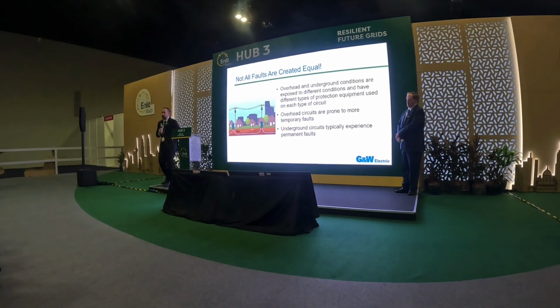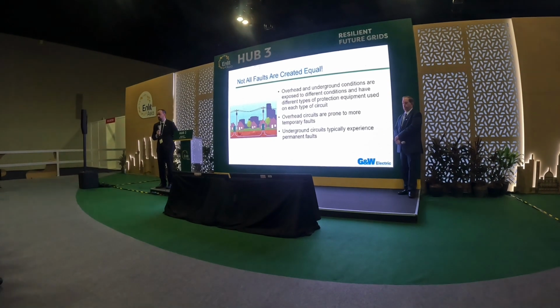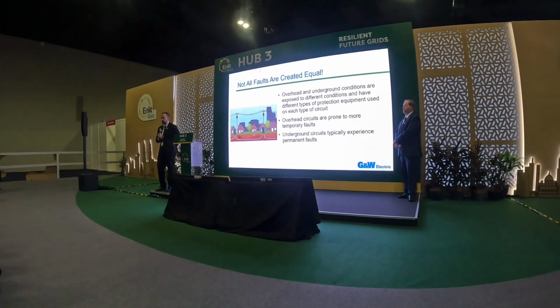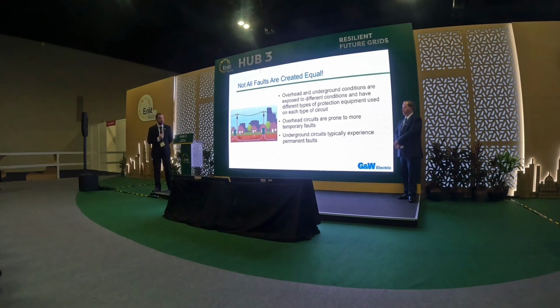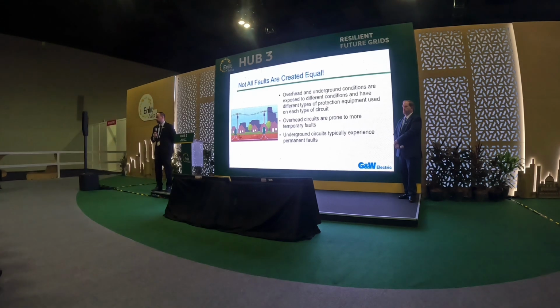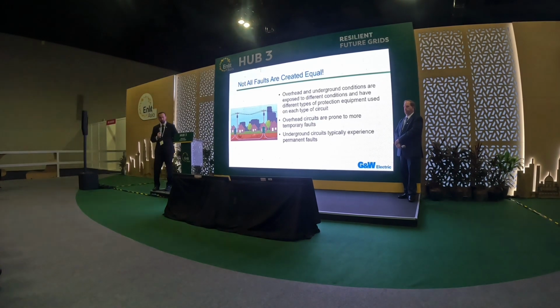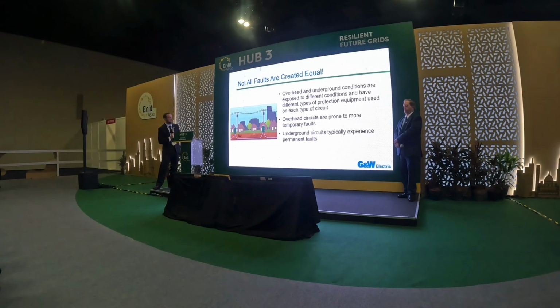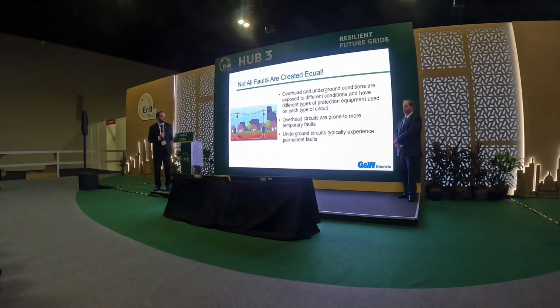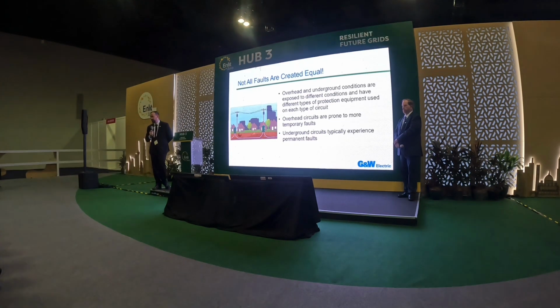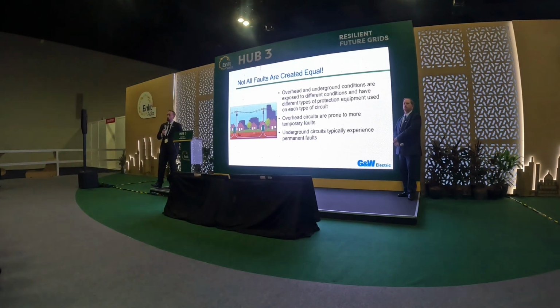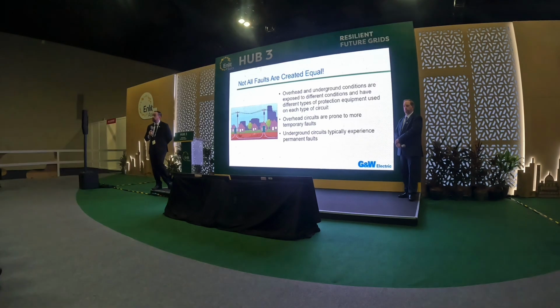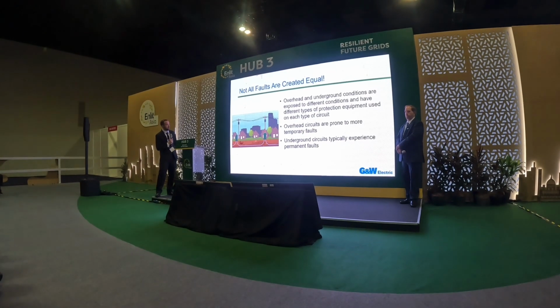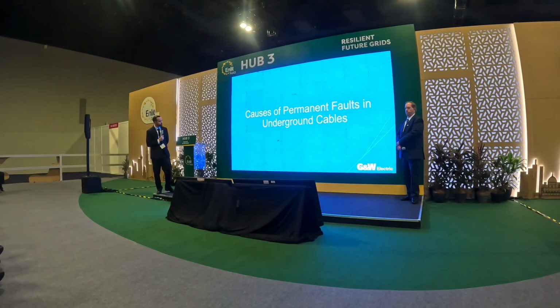So when we're looking at operating both transmission and distribution systems, faults obviously have a major impact on that system, but not all faults are created equal. There are differences in these types of faults, and as a result, the protection equipment used on overhead and underground circuits does have some differences. I want to talk a little bit about that.